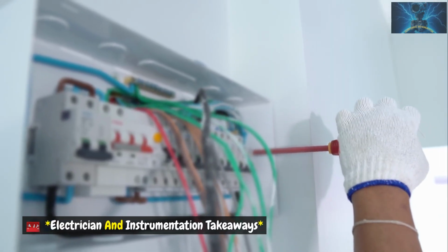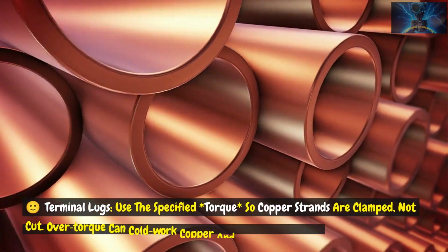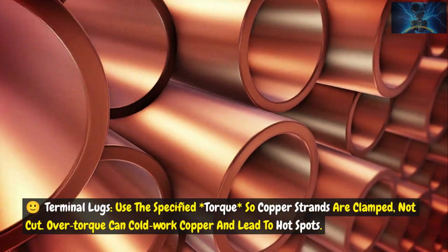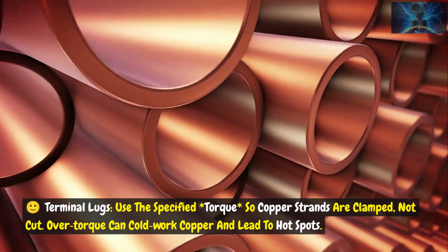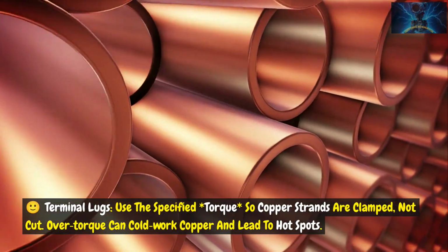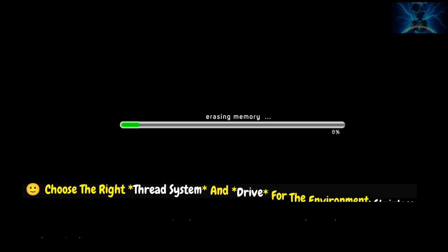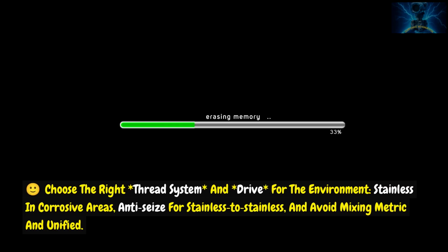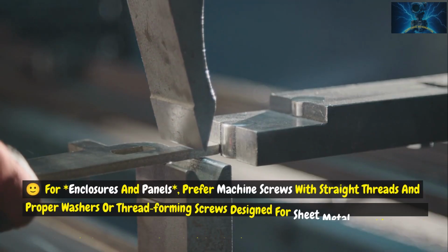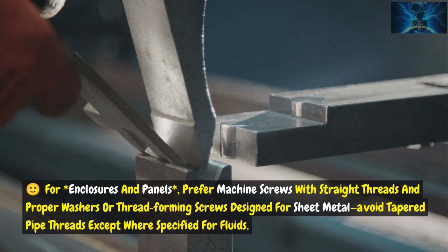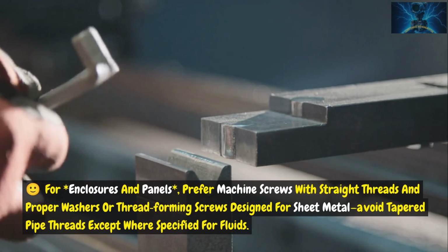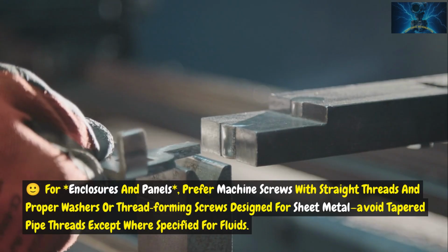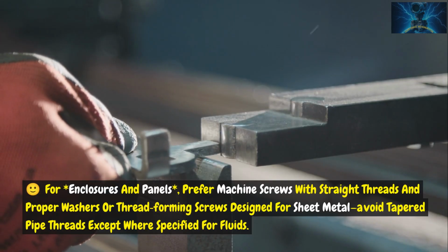Electrician and instrumentation takeaways. Terminal lugs: use the specified torque, so copper strands are clamped, not cut. Overtorque can cold work copper and lead to hot spots. Choose the right thread system and drive for the environment. Stainless in corrosive areas, anti-seize for stainless to stainless, and avoid mixing metric and unified. For enclosures and panels, prefer machine screws with straight threads and proper washers, or thread-forming screws designed for sheet metal. Avoid tapered pipe threads except where specified for fluids.